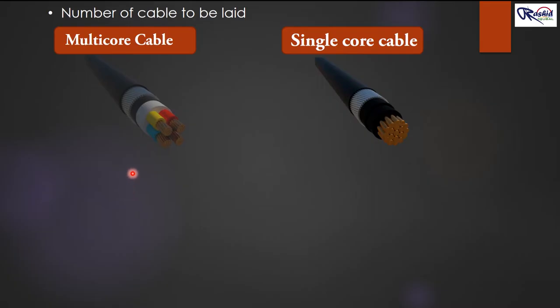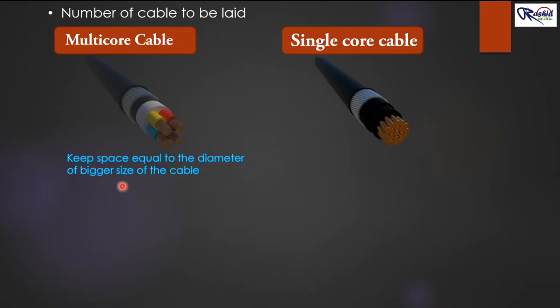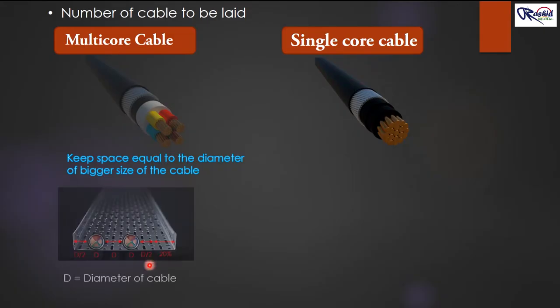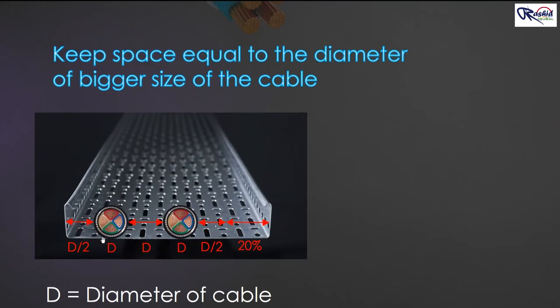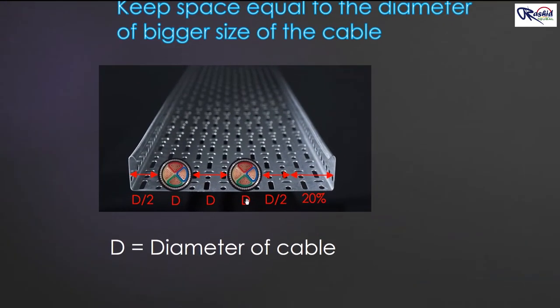The thing we need to keep in mind while calculating the proper size of tray is space — space between cable to cable. For multi-core cable, we keep the space between cable to cable equal to the diameter of the bigger size cable. Here, D is the diameter of the cable. Since both cables have the same size and same diameter, we keep space between cable to cable equal to D. The space between the cable and the flange of the tray is equal to half the diameter, that is D/2, on both sides. Then we keep 20 percent space for future use.